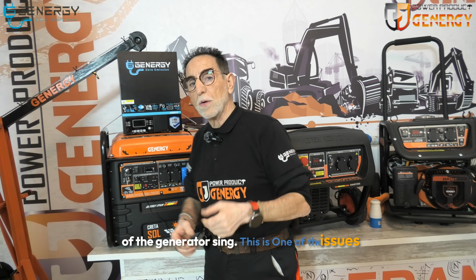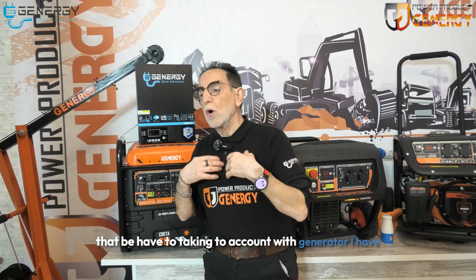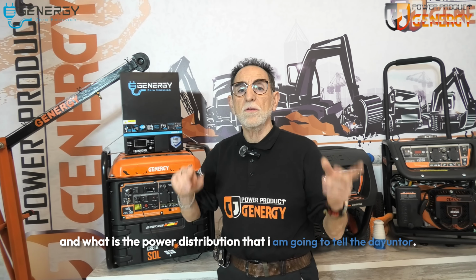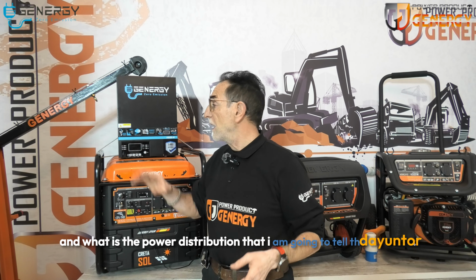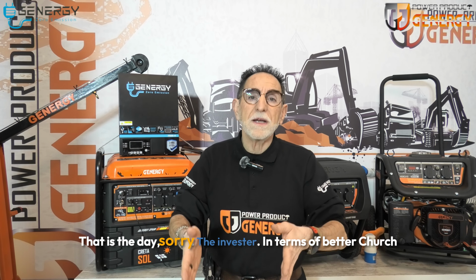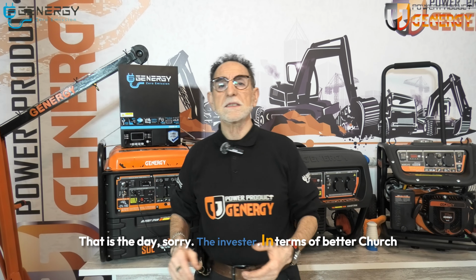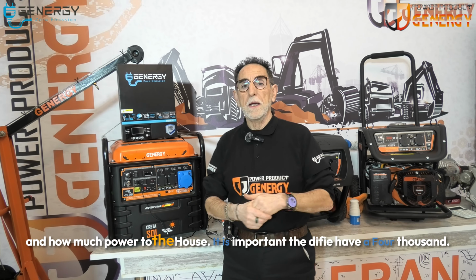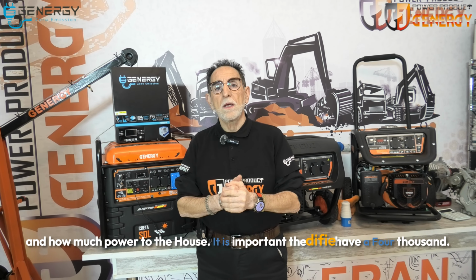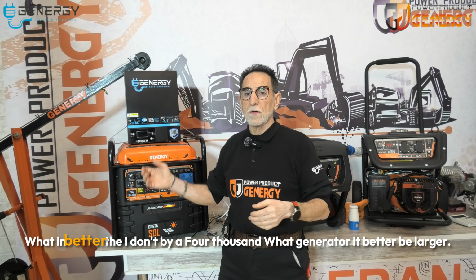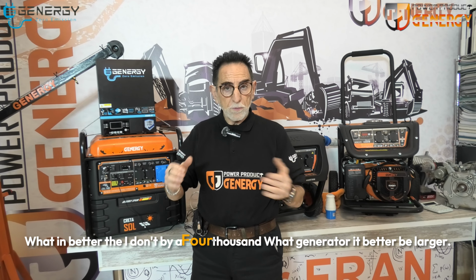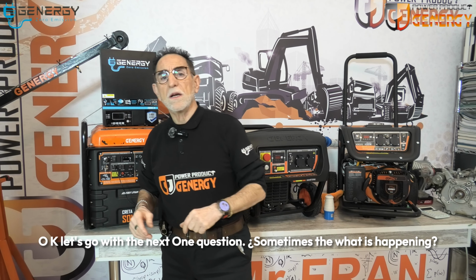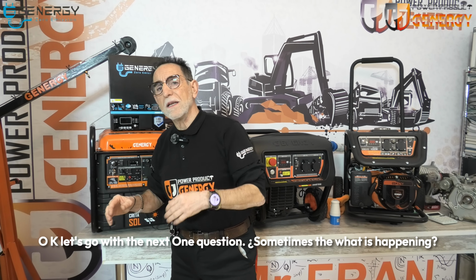This is one of the issues that we have to take into account: which generator I have and what is the power distribution that I am going to tell the inverter, in terms of battery charge and how much power to the house. It is important that if I have a 4000 watt inverter, then I don't buy a 4000 watt generator. It had better be larger. Okay? Let's go with the next one.